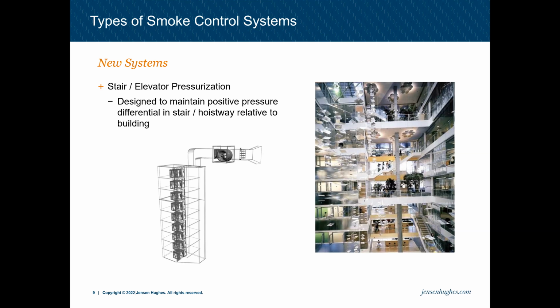And then our elevator pressurization is usually used for the omission of elevator lobbies. Usually in our high-rise buildings, elevator lobbies take up a lot of excess space. So architecturally important to everyone on this call, sometimes we like an open structure or an open floor plan, our elevators opening up into an open corridor or lobby. And so stair pressurization or elevator pressurization allows us to omit the elevator lobbies, still protect our shaft, but allow us to have more of an open floor plan.